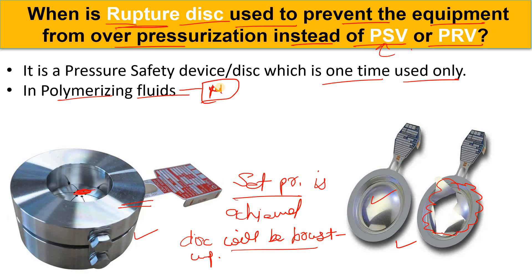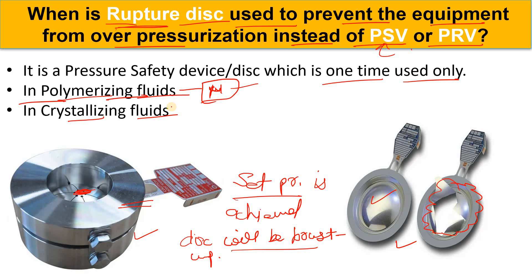The fluid can become highly viscous and can cause blockage or damage to PRVs and PSVs — I have seen this in industry when handling viscous fluids. It also depends on process conditions like set pressure and temperature. When we handle viscous fluids, corrosive fluids, or crystallizing fluids, we prefer to use the rupture disk, because in crystallizing fluids when temperature goes down the fluid could solidify and damage or block your PSVs and PRVs.